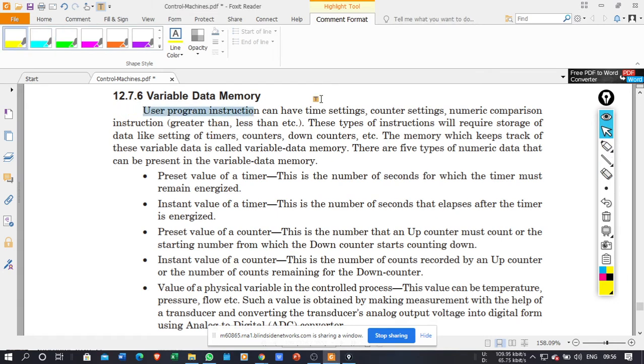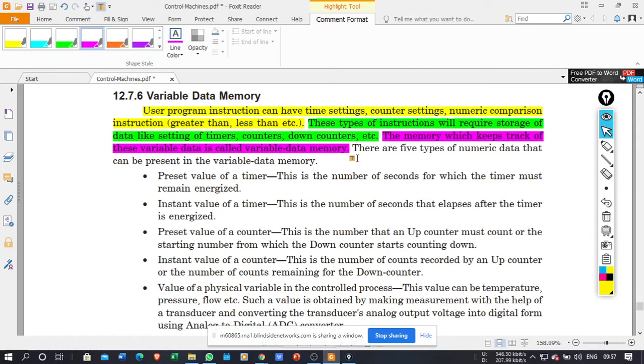User program instructions can have time setting, counter setting, numerical comparison like less than, greater than, etc. These instructions require storage of data such as the setting of the timer or counter. So the data needs to be stored temporarily, keeping track of the timer setting or counter setting. This memory which keeps track of variable data is called the variable data memory, a special dedicated memory for these variables.